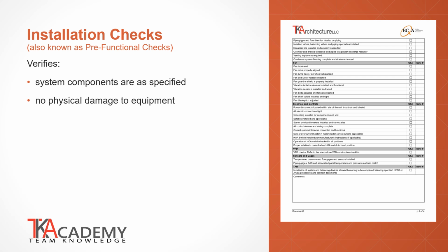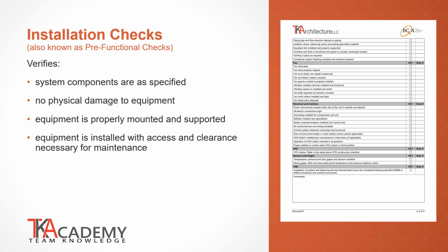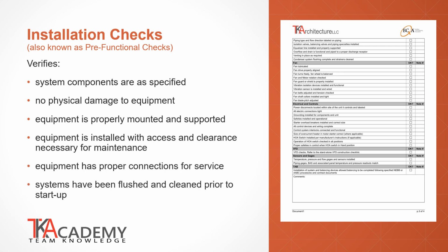The commissioning provider will verify that the equipment is properly installed, mounted, and supported correctly, and that the equipment is installed with access clearances necessary for maintenance. They will also ensure that the equipment has proper connections for service and that the appropriate systems have been flushed and cleaned prior to the startup. All these items are per the installation checklist and are checked off as they are verified on site. Incomplete items are provided to the contractor for action items to be addressed.